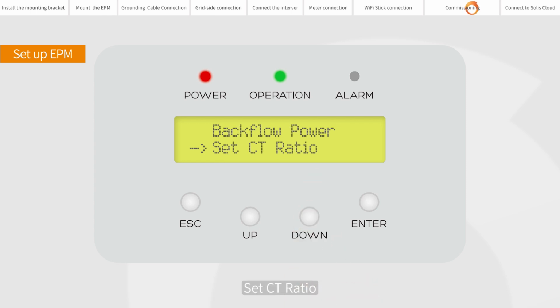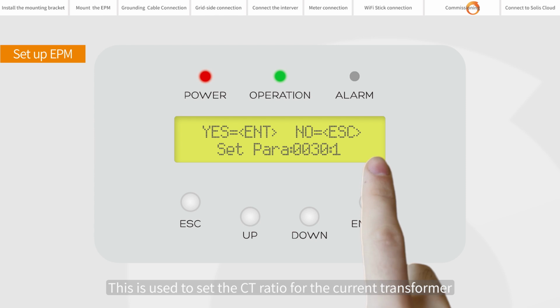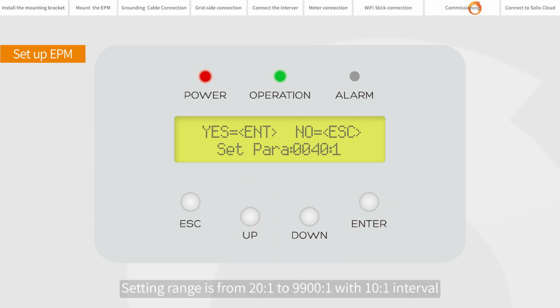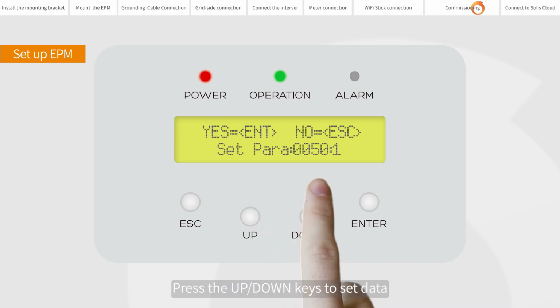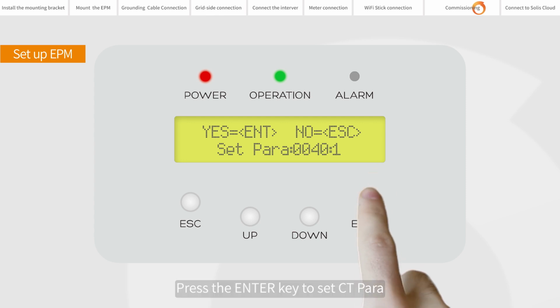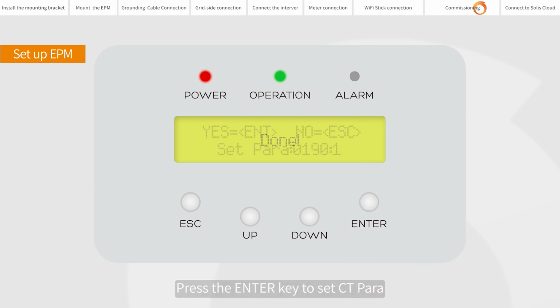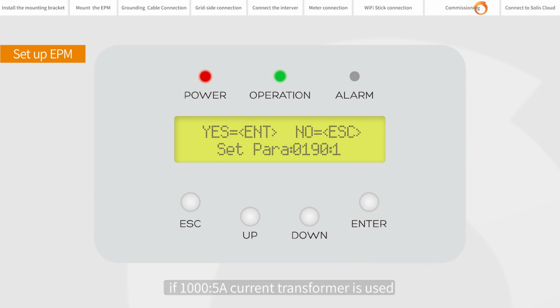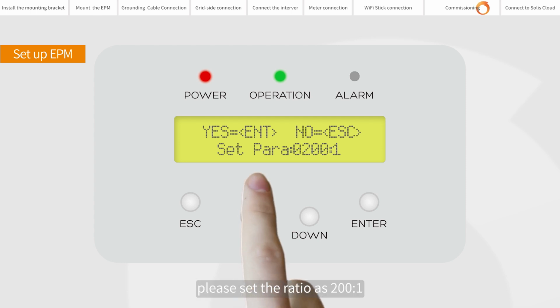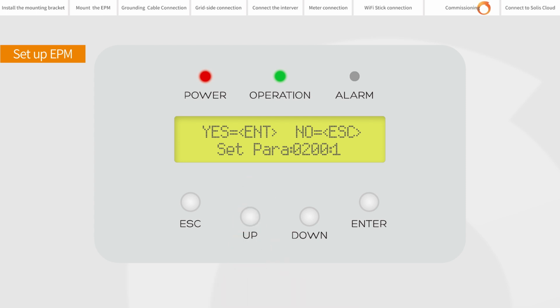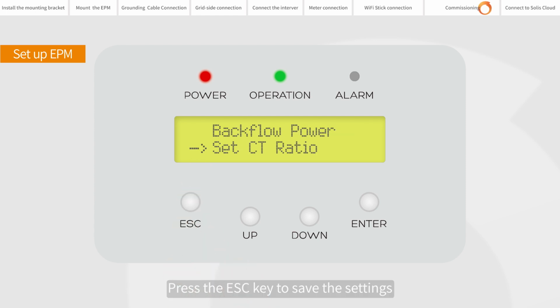Advanced settings, set CT ratio. This is used to set the CT ratio for the current transformer. Setting range is from 20:1 to 9900:1 with 10:1 interval. Press the up or down keys to set data. Press the Enter key to set CT para. For example, if a 1000 to 5 A current transformer is used, please set the ratio as 200 to 1. Press the ESC key to save the settings and return to the previous menu.